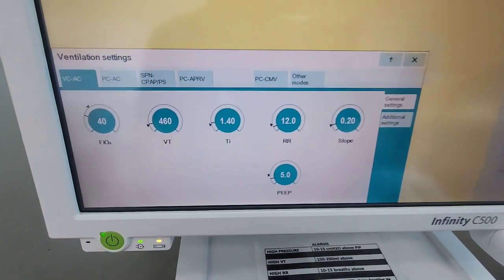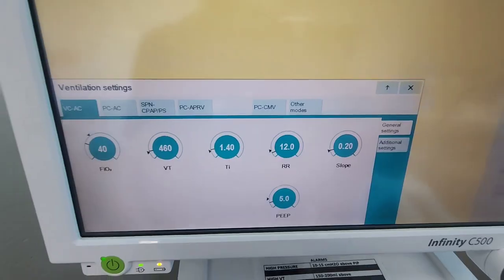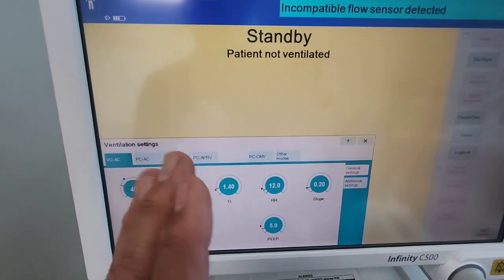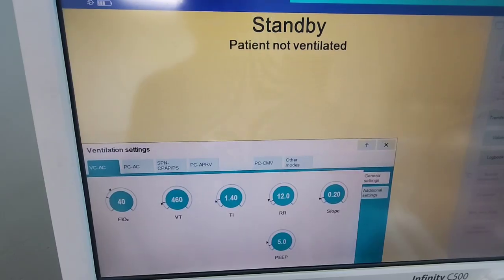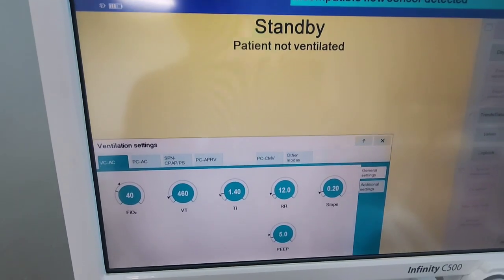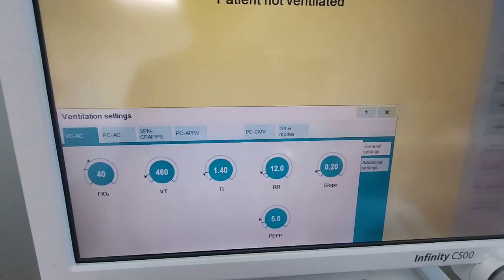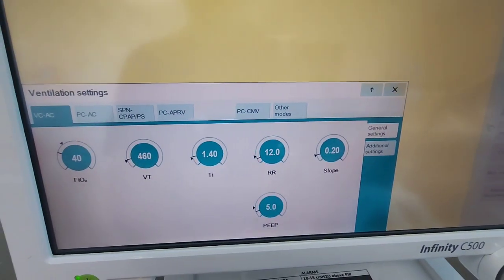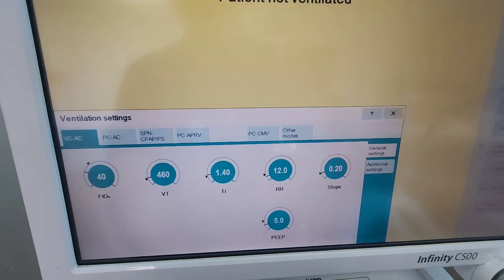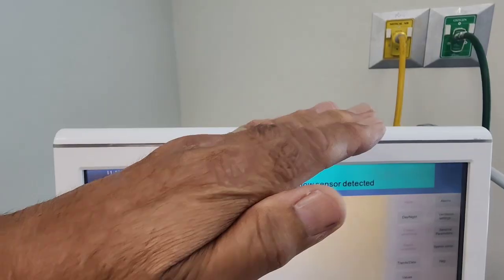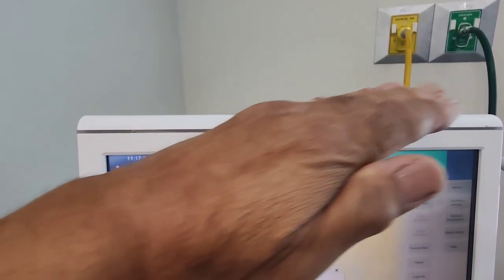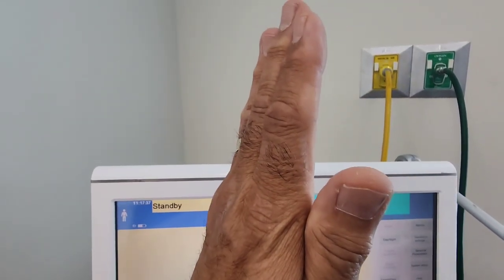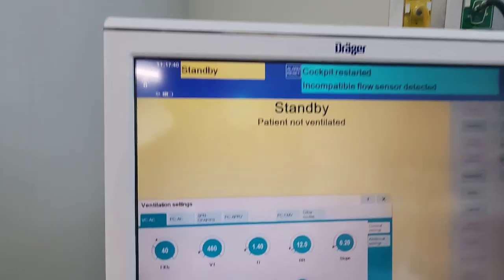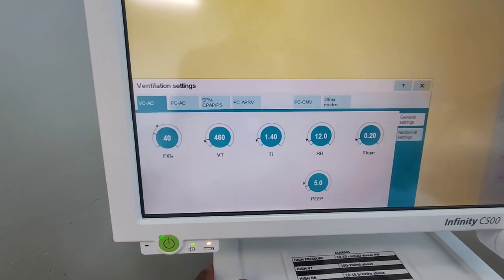Okay, a slope. If you think of a slope on a hill, the steeper it is, it indicates how quickly it's going to rise to the top. But if you have a really low, very slow slope, right now it's 0.2 seconds. If you have it at 1 second, you can see that the slope is more like this. The air, the flow, is going to take a little longer to get into the lungs, as opposed to a very quick slope. Okay, we'll talk about that later. But anyhow, those are some settings there.